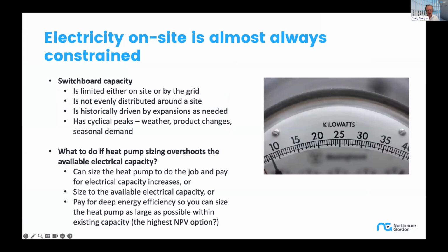In our studies of electrification and energy audits, we find electricity on site is almost always constrained one way or another. It's either limited by the site or the grid supplying it, or it's unevenly distributed around the site in switchboard capacity. Switchboard location and capacity is often driven by expansions to production, minimizing capex, so they steal power from other switchboards. Individual switchboards have cyclical peaks, whether weather-driven, affecting chiller systems, or product lines, or seasonal demand like food and beverage driving seasonal peaks.